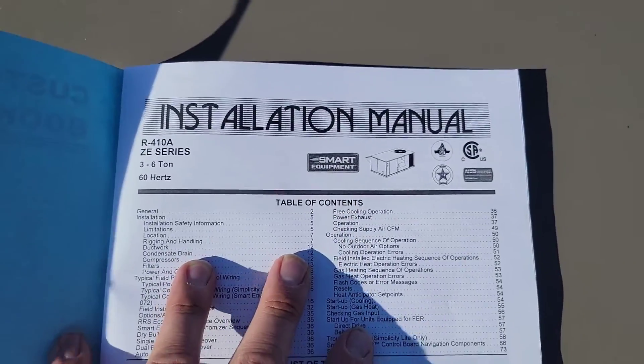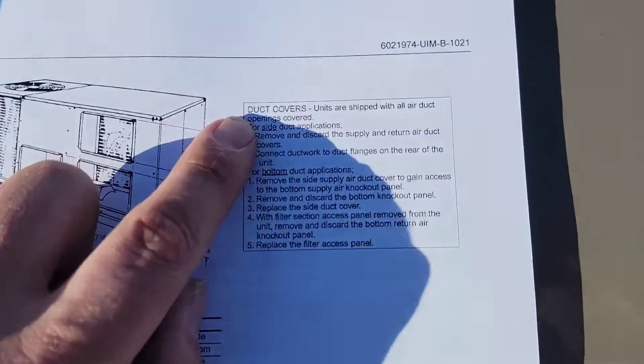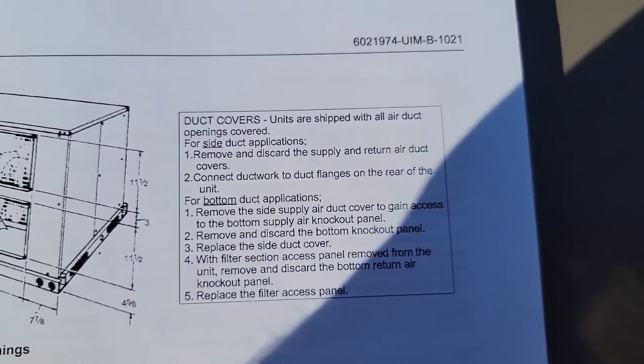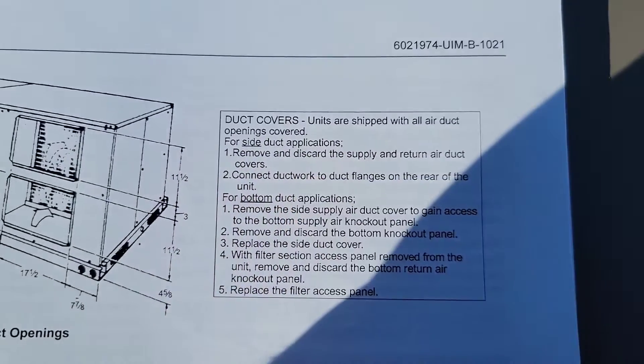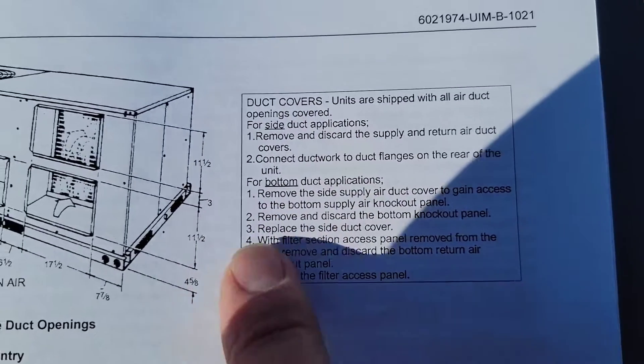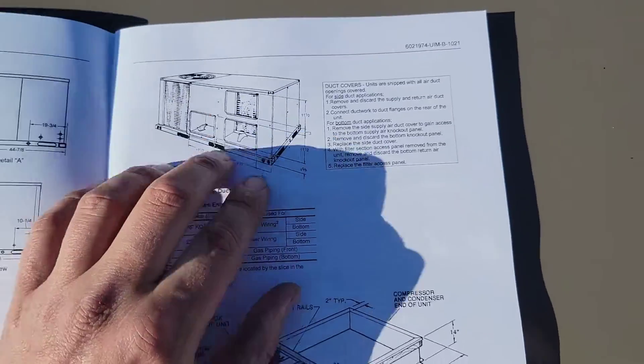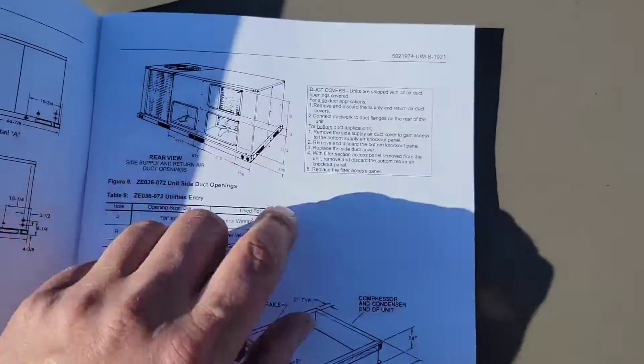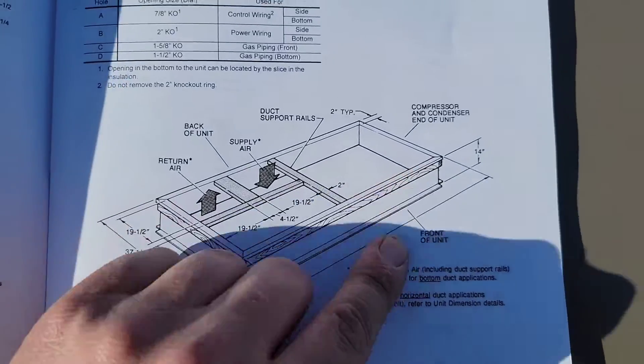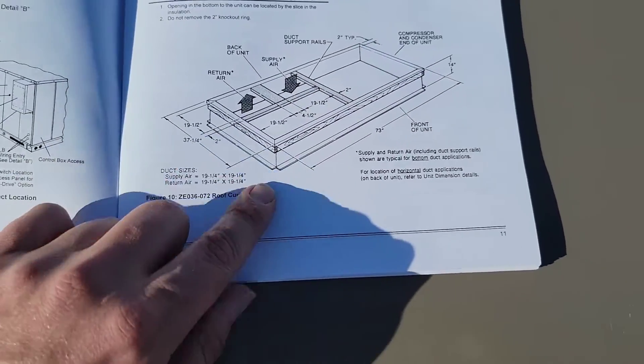This is the manual and it should be your best friend too. If you read this installation manual, you will learn a lot of information about the piece of equipment you are installing. Like duct covers — units are shipped with all air duct openings covered. For side duct applications, remove and discard the supply and return air duct covers. For bottom duct applications, remove the side supply air duct cover to gain access to the bottom supply air knockout panel. If you look at the first few pages, you can learn about the curb and see the supply and return openings with actual dimensions.